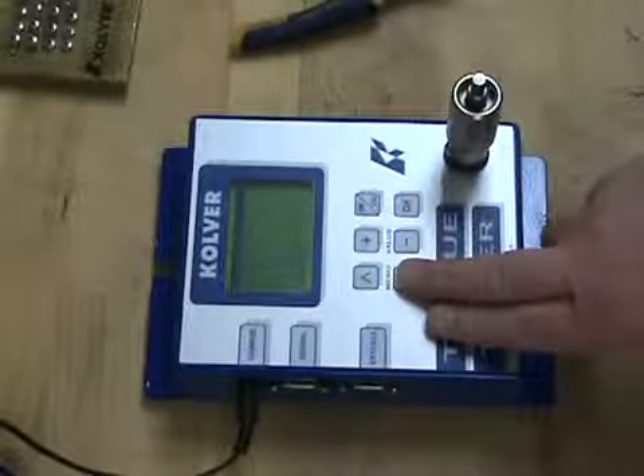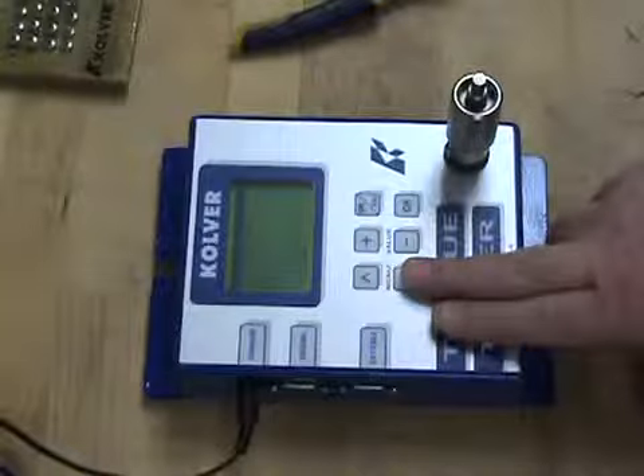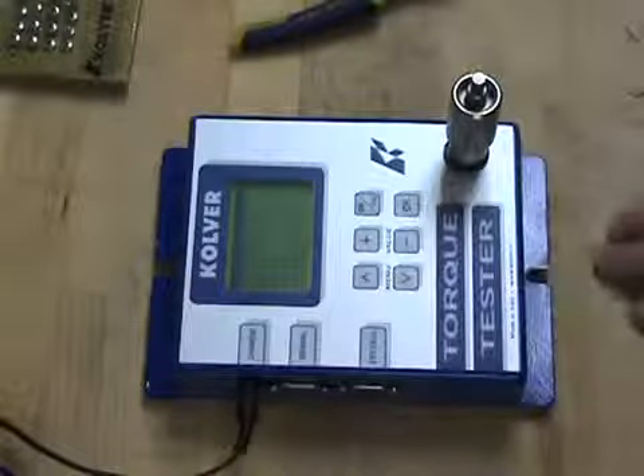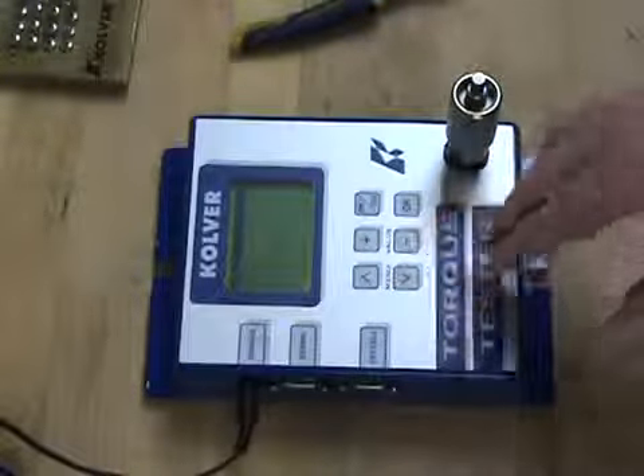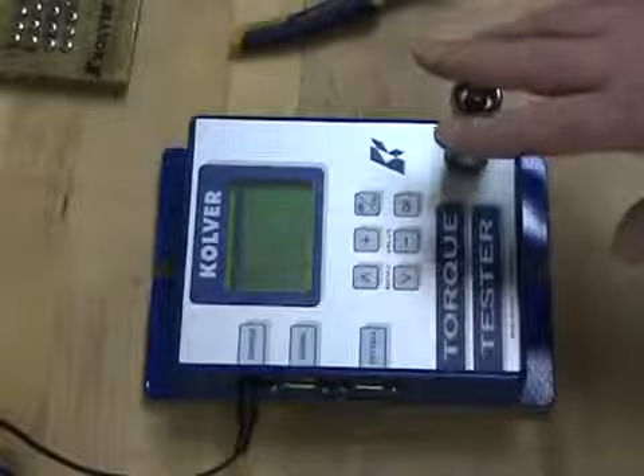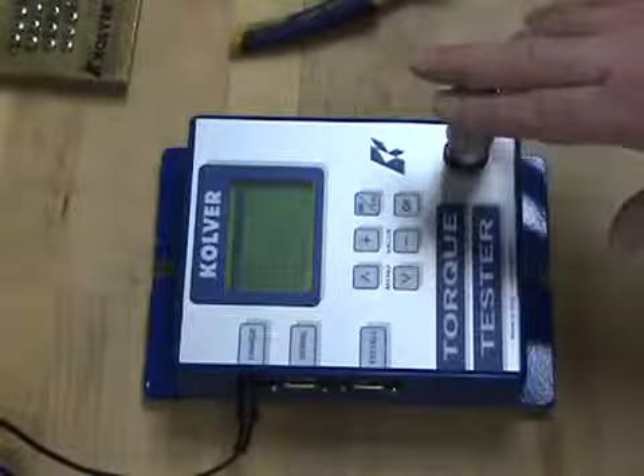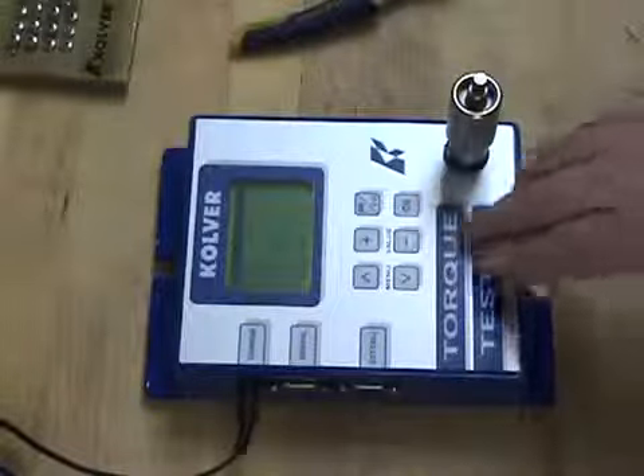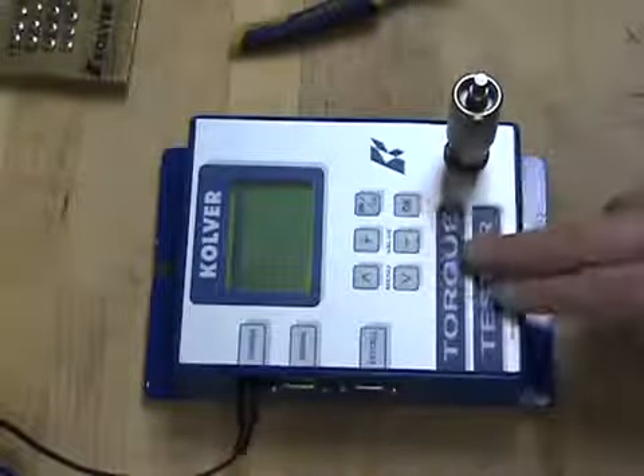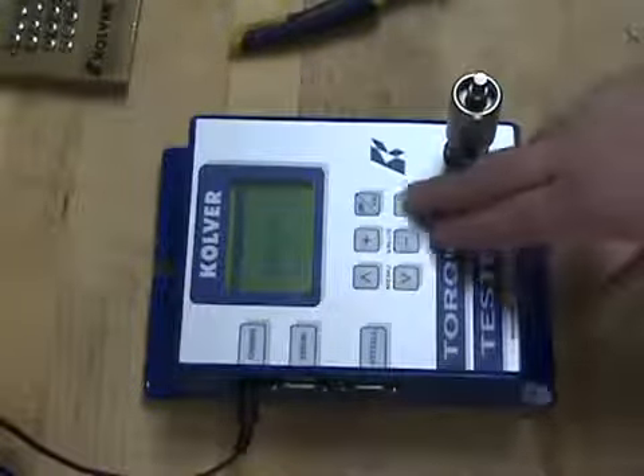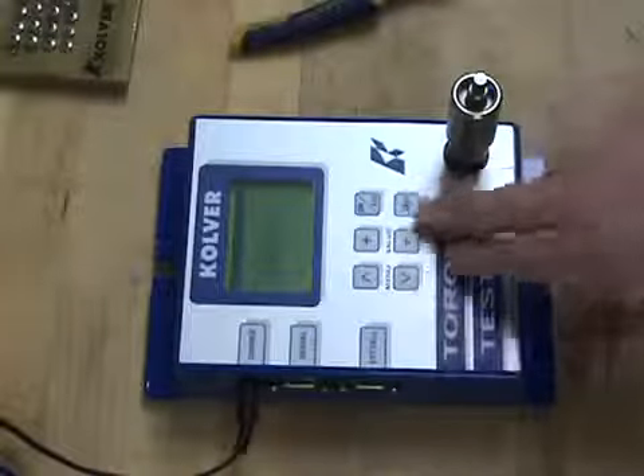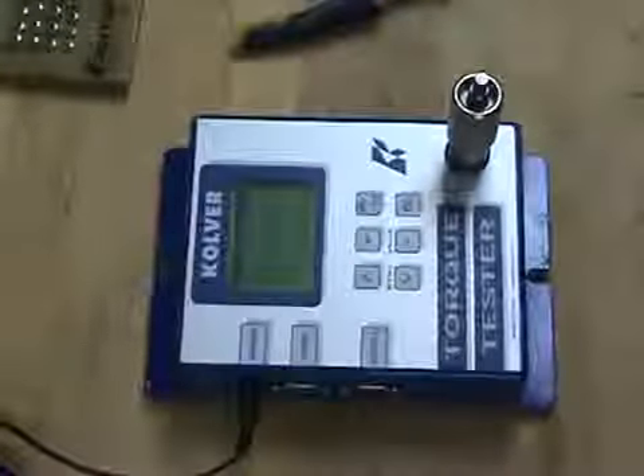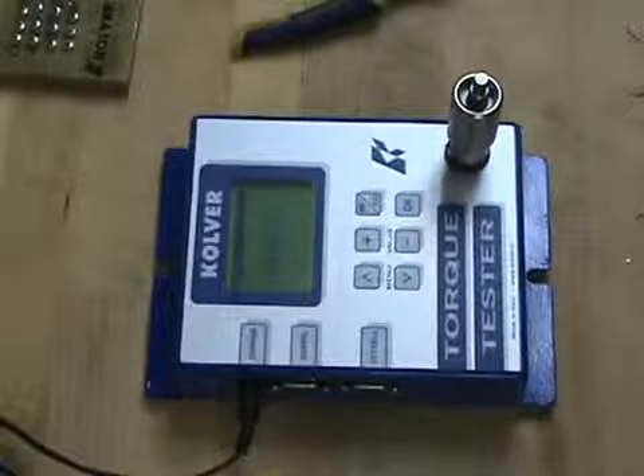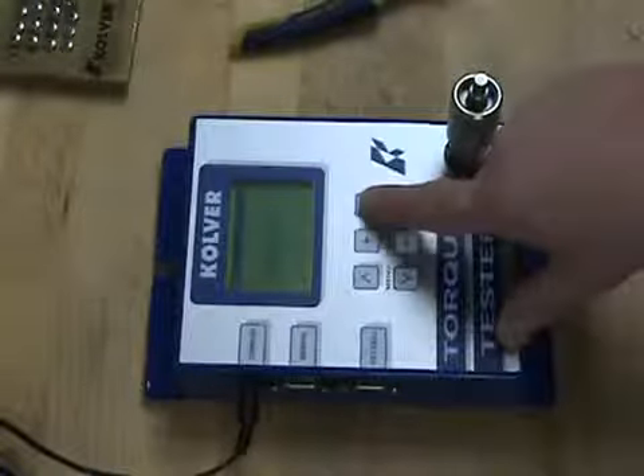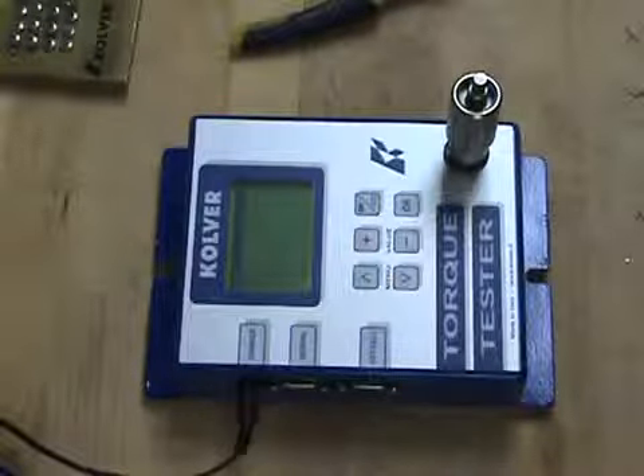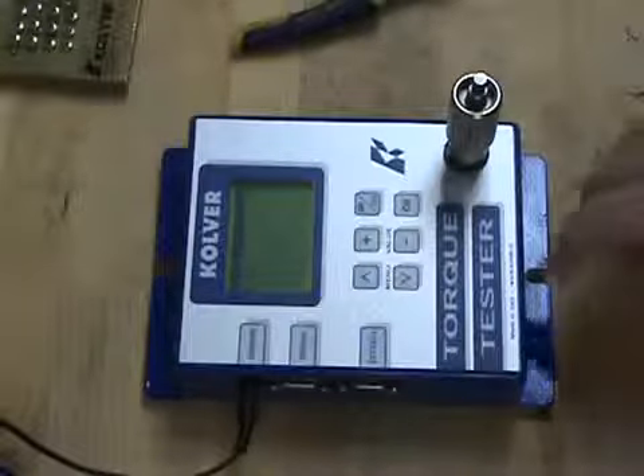You can select a language, and in setup we have 0, which if the numbers aren't at 0 when you start, you want to re-zero, and we would press OK to 0, and then press OK one more time, and this will actually reset the transducer to a 0 point. You can click OK or Escape to go back to our setup window.